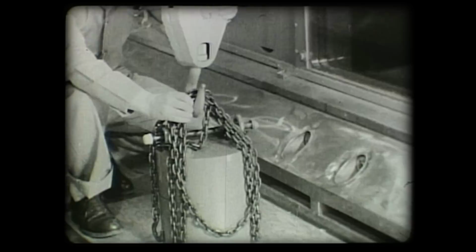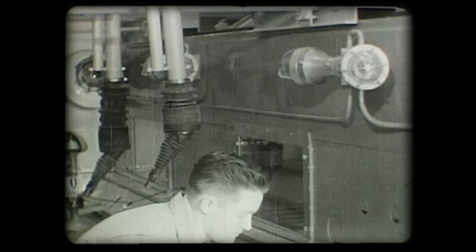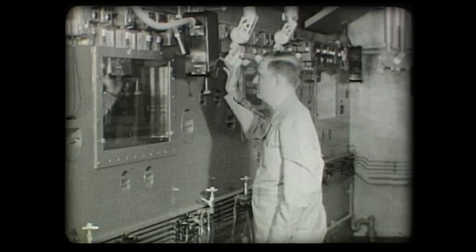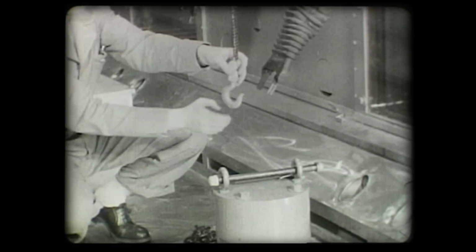These heavily shielded samples have to be hoisted over the wall. Some of the caskets will weigh up to 1,300 pounds. This one weighs about 400. The manipulators were designed by the Argonne National Laboratory and are called master slaves. They are actually mechanical extensions of the operator's hands into the cave. The master slave can handle weights of up to about 7 pounds, so each unit is used in conjunction with a 500-pound chain hoist.